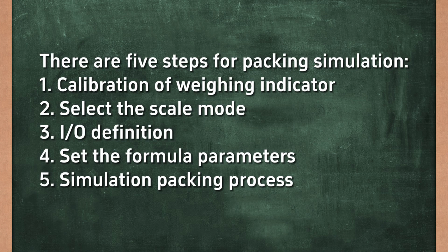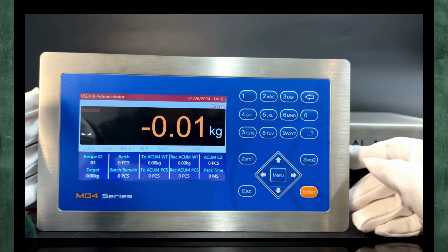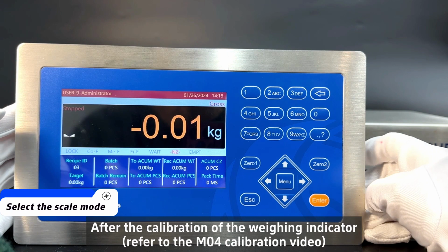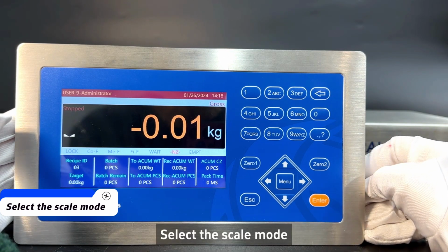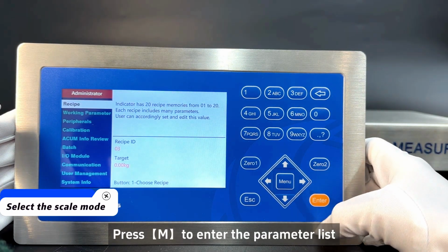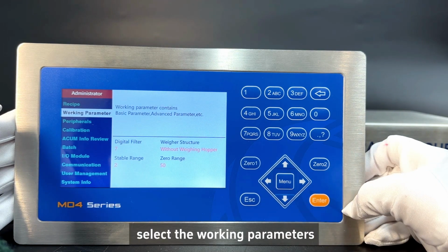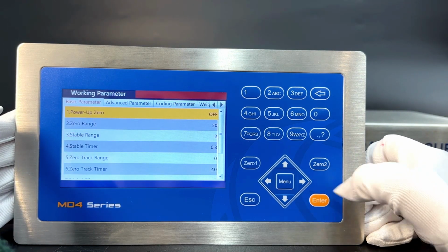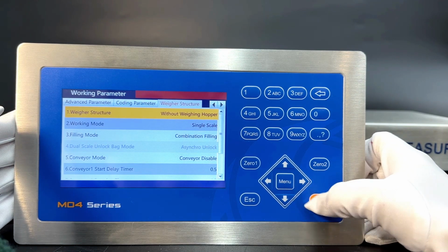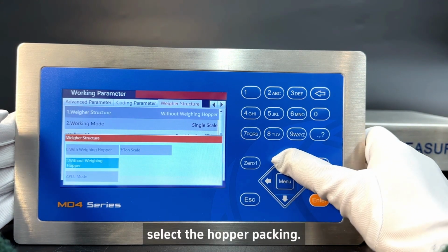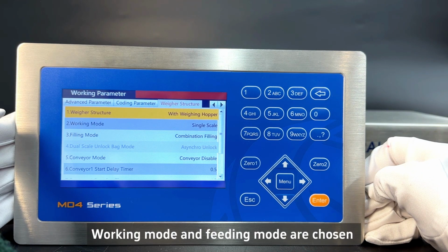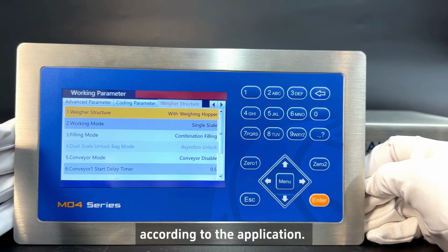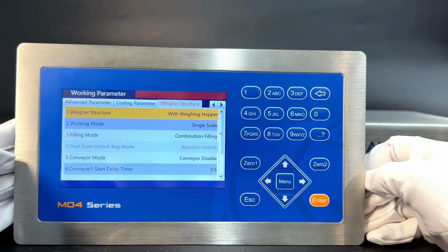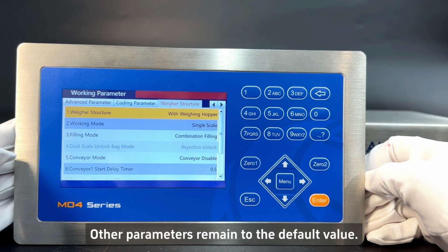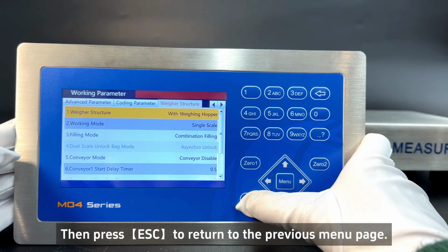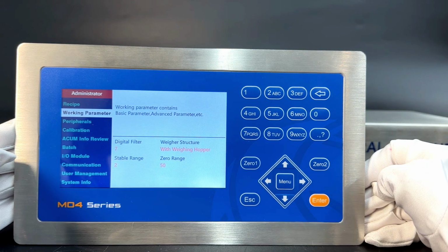Fifth, simulation packing process. After the calibration of the weighing indicator, select the scale mode. Press Menu to enter the parameter list. Select the working parameters. Press Enter. Find the scale structure. Select the hopper packing. Working mode and feeding mode are chosen according to the application. Other parameters remain to the default value. Then press ESC to return to the previous menu page.